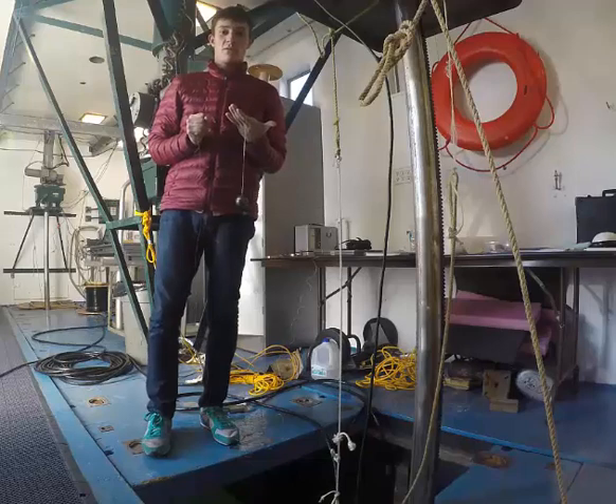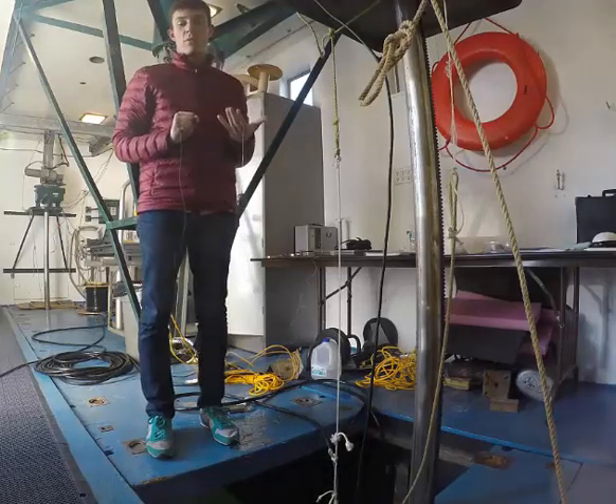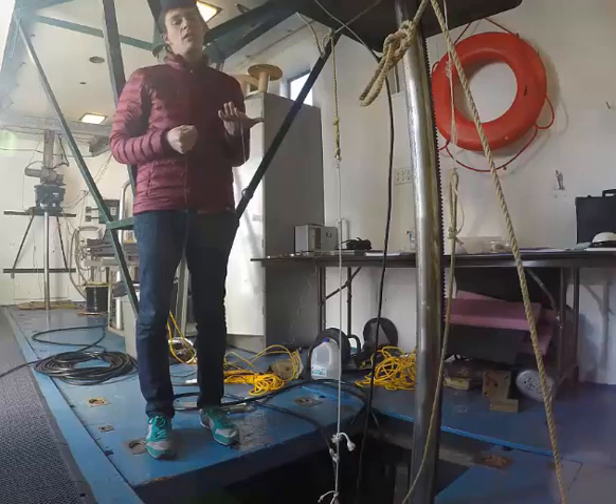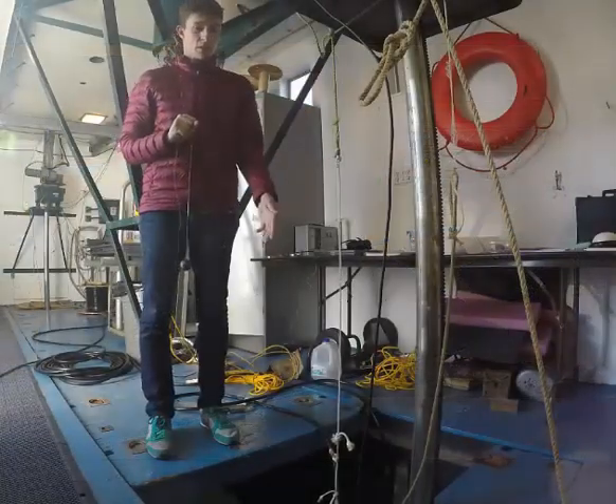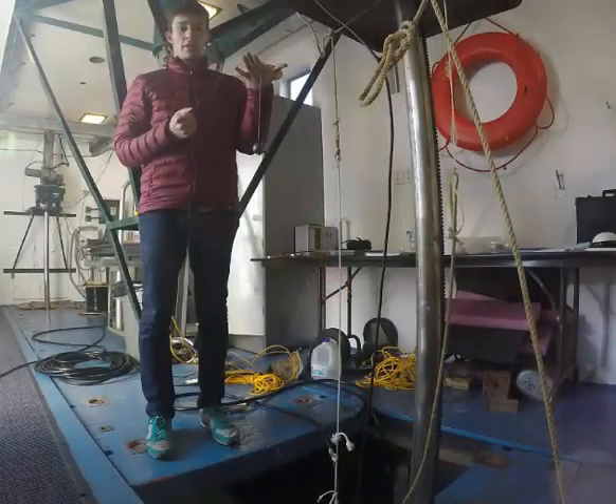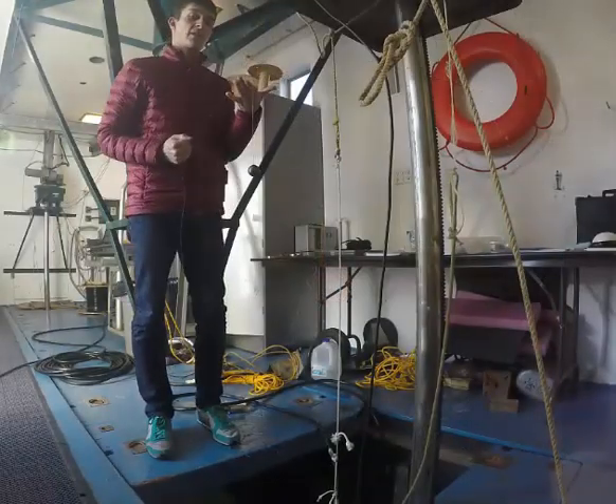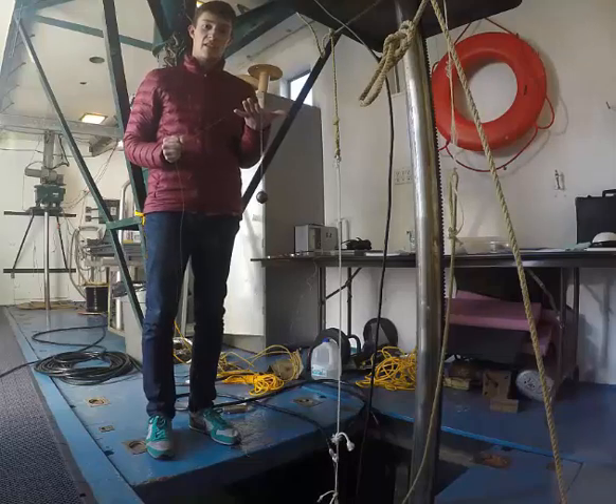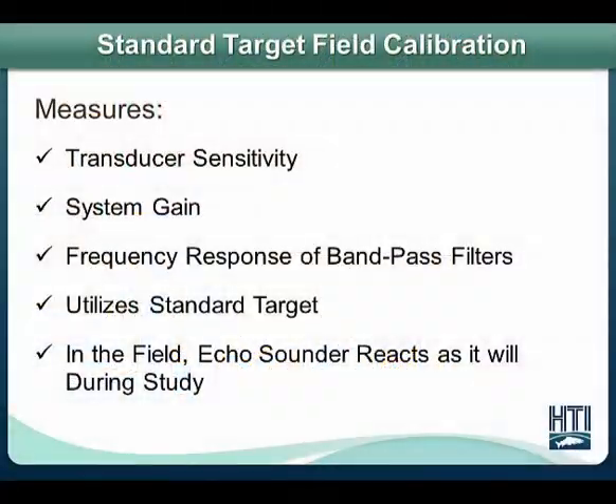Hello, in this video we're going to show you how to perform a standard target field calibration of an HTI Model 241 echo sounder using a split beam transducer in the water and a standard target sphere. The purpose of performing a calibration test is to measure your transducer sensitivity, your system gain, and frequency response of bandpass filters in an environment that is similar or the same as your field study.